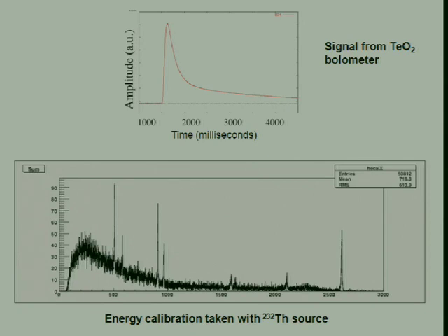So this gamma ray is at 2.6 MeV. Here are 2 gamma rays that are produced as a result of the pair production effect. So this 2.6 MeV gamma ray goes into the crystal. It produces an electron-positron pair. The positron eventually slows down and annihilates, makes 2 511 keV photons. If I catch both of them, I end up measuring the full 2.6 MeV. If one of them escapes, I get a line at 2.6 minus 0.5 or 2.1 MeV. If both of them escape, I get 2.6 minus 1.022, 1.5 MeV. Okay, so this is the first escape, second escape peak.